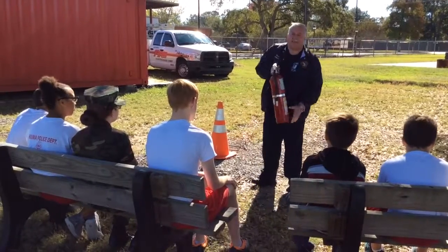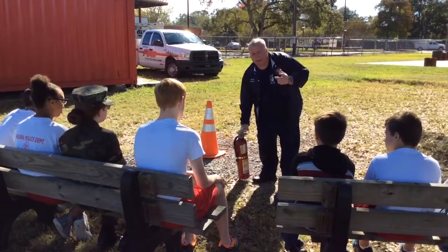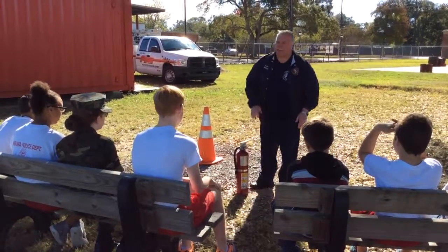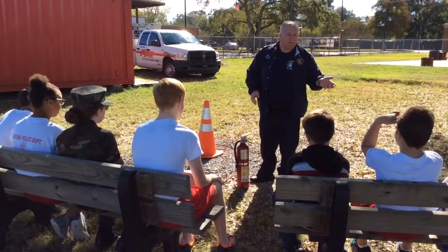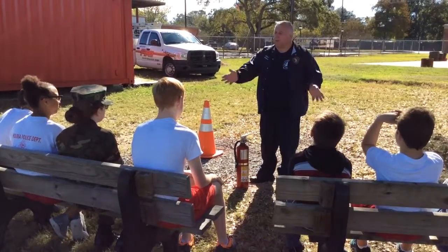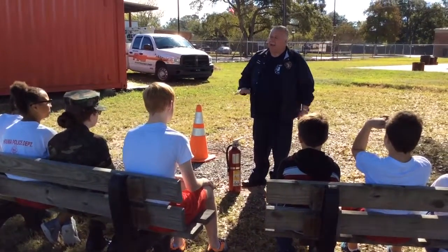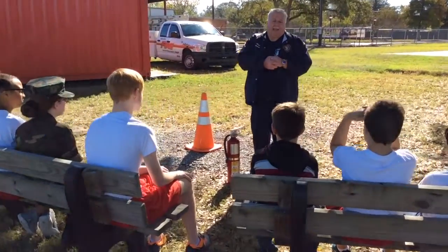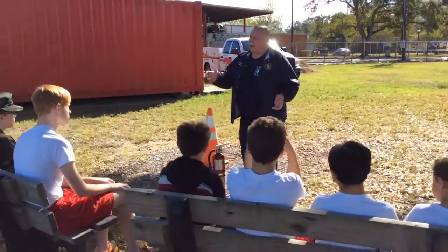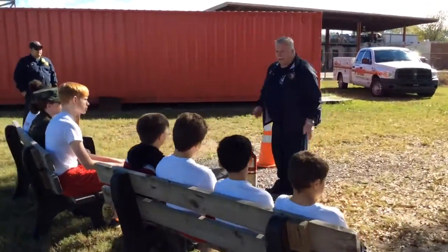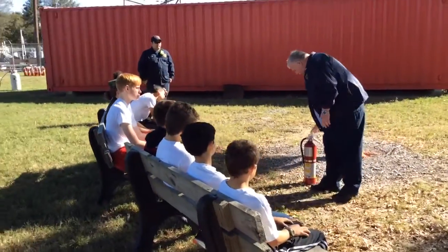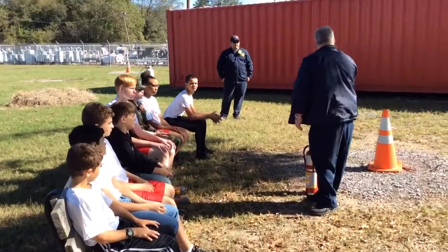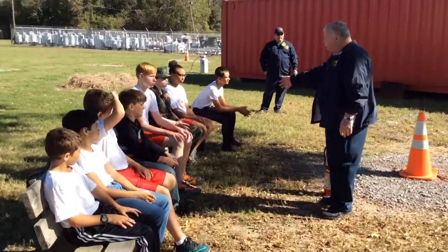So this extinguisher is good for a Class A, B, or C fire, okay? So they call it a multi-purpose dry chemical. So it can pretty much be used on any type of fire. A lot of places you're going to find this type of extinguisher because it's good for any type of fire and you don't have to think about it, okay? Now they also, the different types of fire extinguishers, this is dry chemical. Most of the time, dry chemical is Class A, B, and C, okay?